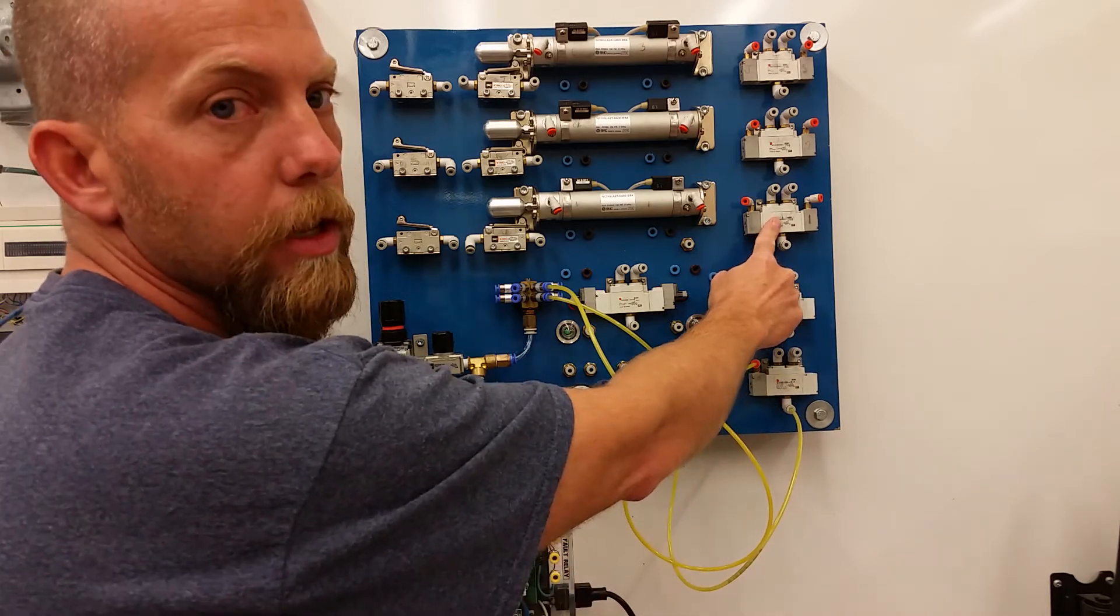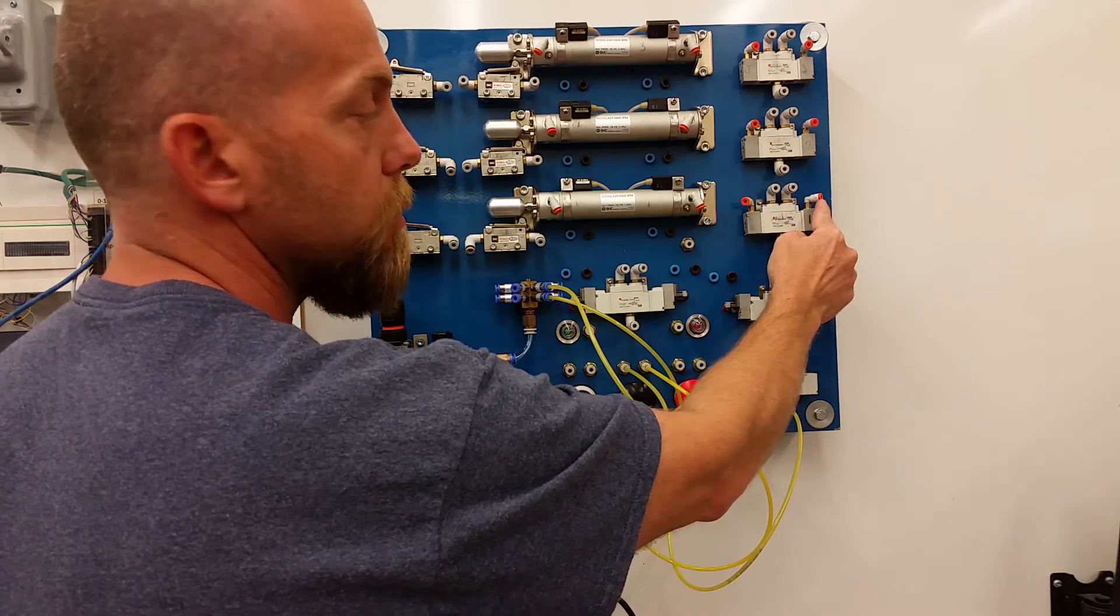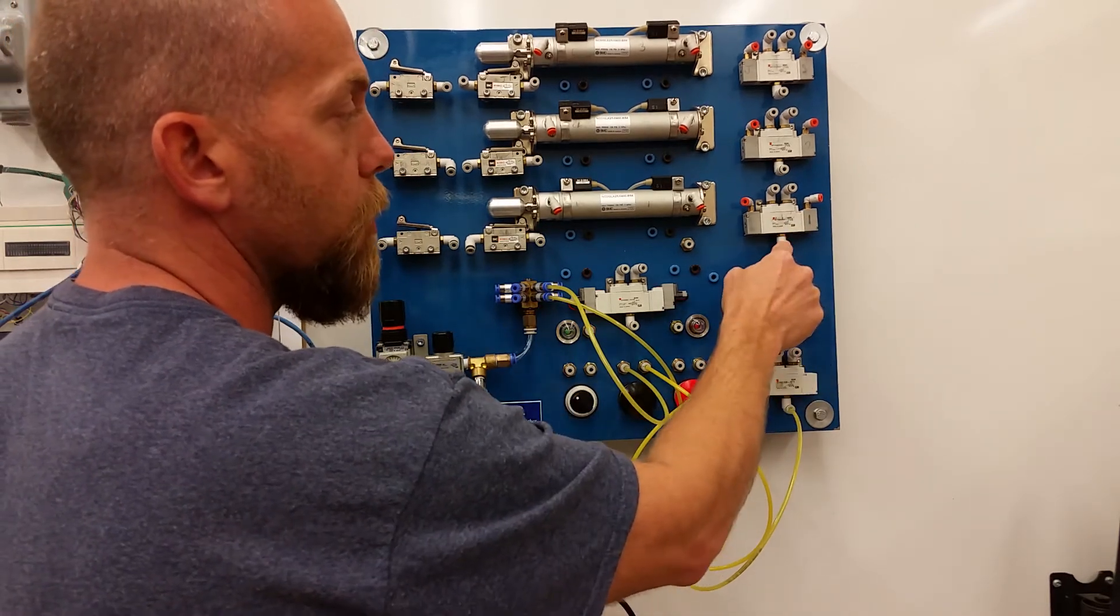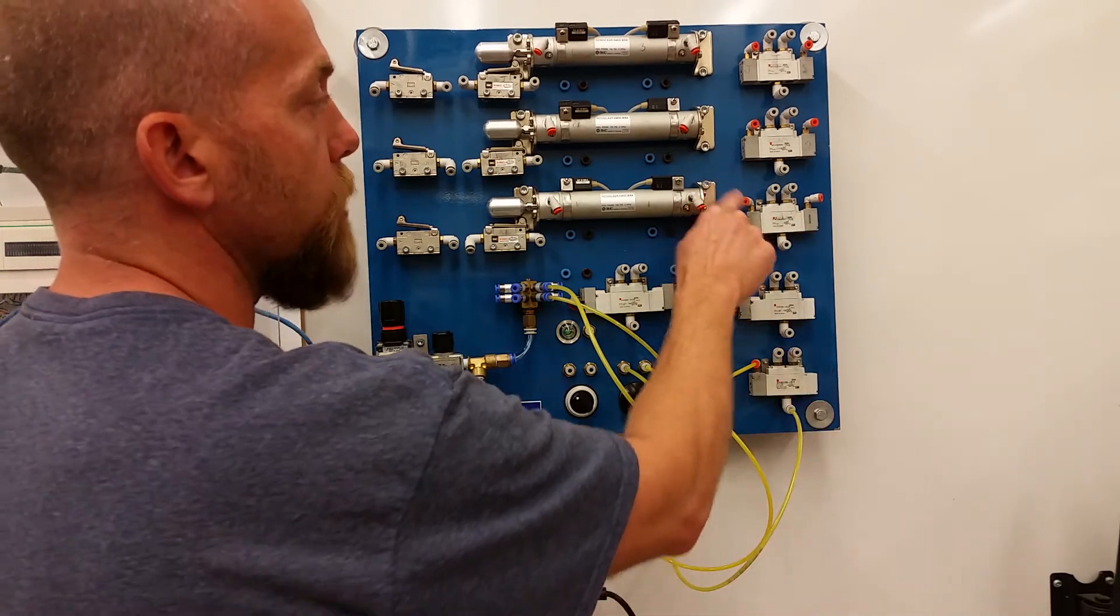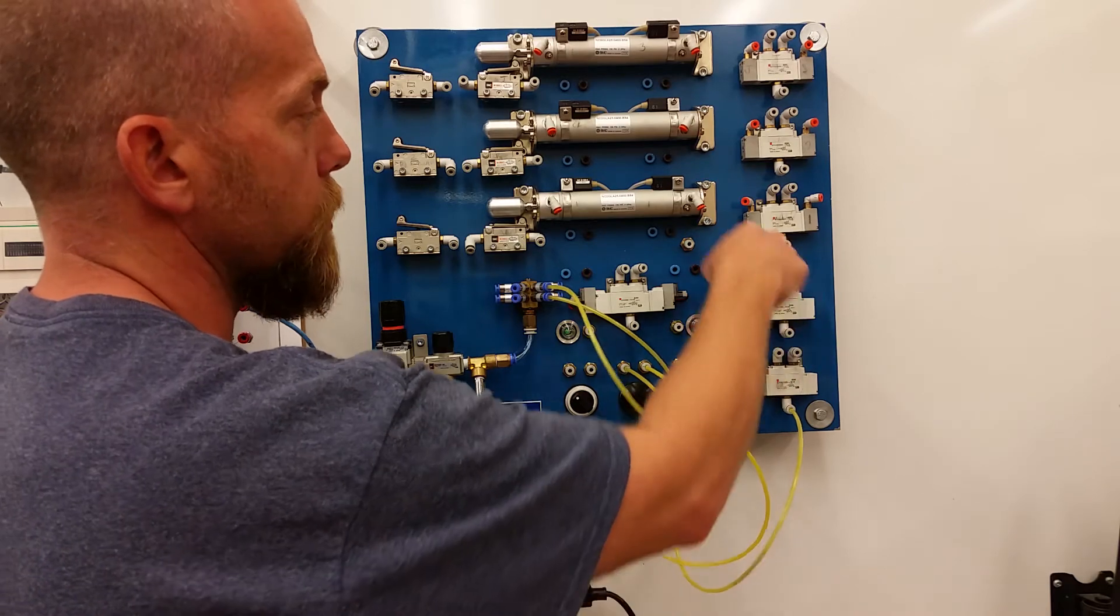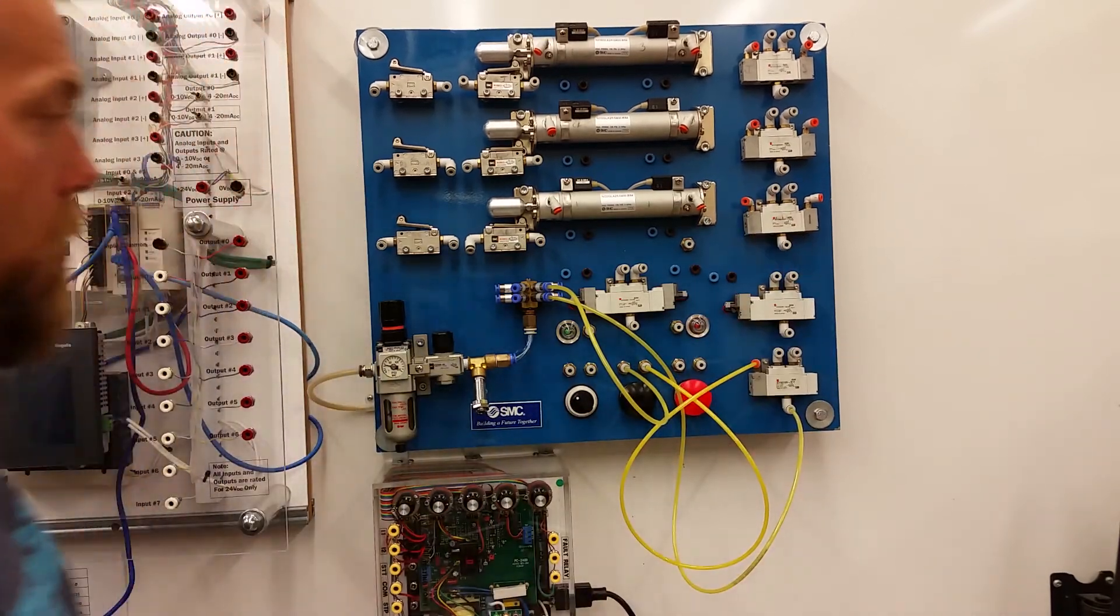And that this one has a spring to always return the air to this port. These guys will stay there for weeks and months until the next signal comes in. So if that was your last signal, you come back the next day, air will go from here to here. If your last signal of your lab came into this port, well then when you come back the next day, air will go from here to here.